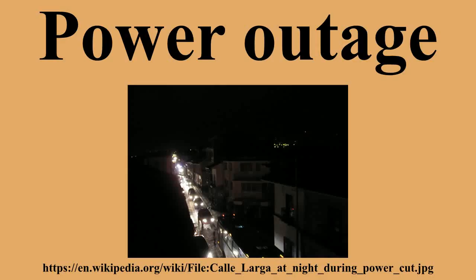To maintain supply frequencies within tolerable limits during this process, demand must be reconnected at the same pace that generation is restored, requiring close coordination between power stations, transmission and distribution organizations. Blackout inevitability and electric sustainability. Self-organized criticality.